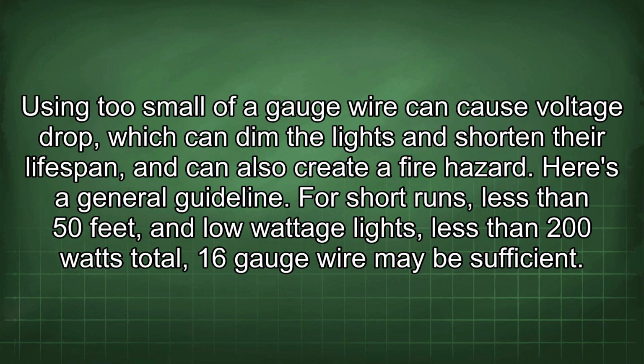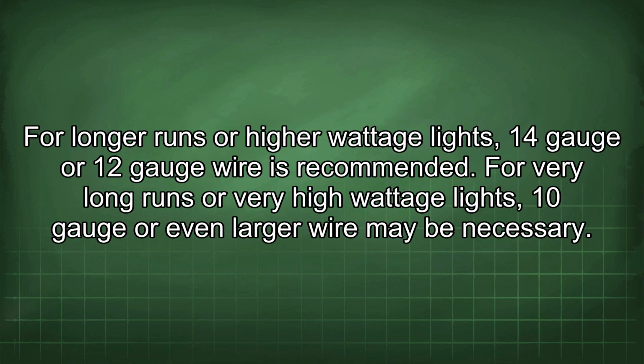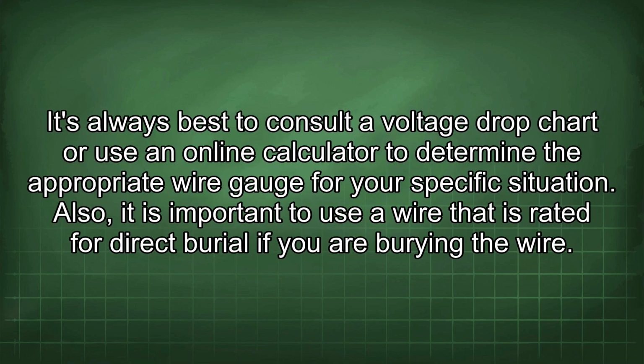Using too small of a gauge wire can cause voltage drop, which can dim the lights and shorten the lifespan, and can also create a fire hazard. Here's a general guideline. For short runs, less than 50 feet, and low wattage lights, less than 200 watts total, 16-gauge wire may be sufficient. For longer runs or higher wattage lights, 14-gauge or 12-gauge wire is recommended. For very long runs or very high wattage lights, 10-gauge or even larger wire may be necessary.